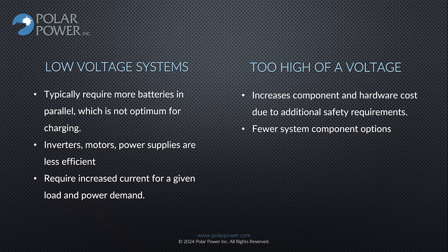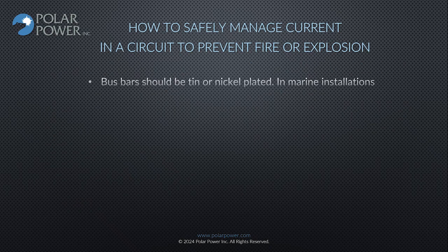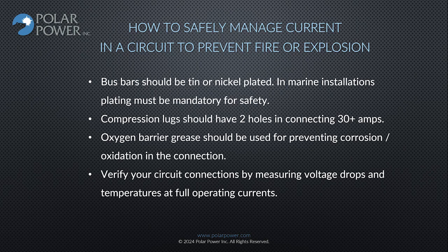Too high of a voltage increases component and hardware cost due to additional safety requirements, and gives fewer system component options. How to safely manage current in a circuit to prevent fire or explosion: Bus bars should be tin or nickel plated. In marine installations, plating must be mandatory for safety. Compression lugs should have 2 holes in connecting 30 amps. Oxygen barrier grease should be used for preventing corrosion and oxidation in the connection. Verify your circuit connections by measuring voltage drops and temperatures at full operating currents.